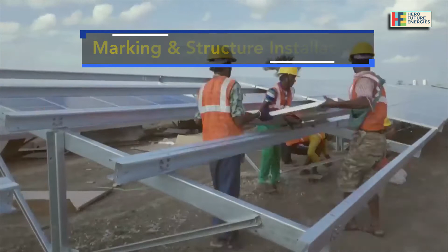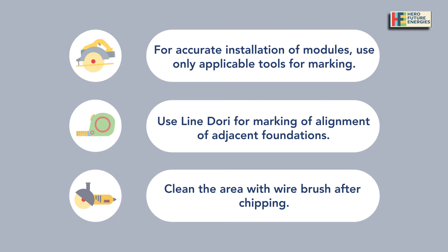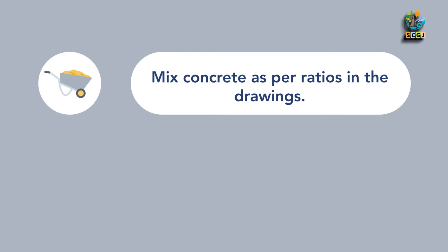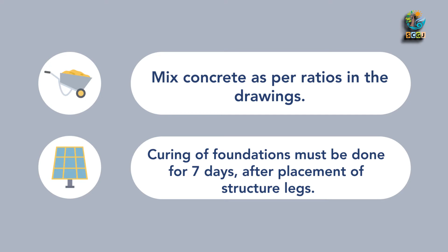For accurate installation of modules, use only applicable tools for marking. Use line dori for marking of alignment of adjacent foundations. Clean the area with a wire brush after chipping. Mix concrete as per ratios in the drawings. Consistent curing of foundations must be done for 7 days after placement of structure legs.